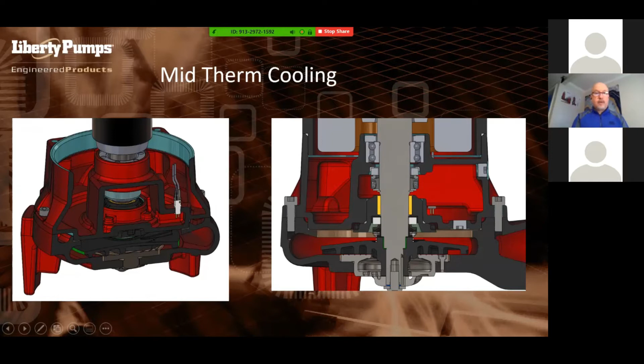And then there's a smaller chamber of oil for the seal area and the seal leak detection probe, so for the lower seal. And I'll show you here a couple other manufacturers' designs, but you can see these are completely enclosed or isolated plates. So you've got an upper chamber of oil and a lower chamber of oil. So anything that's being pumped at a lower temperature might be dissipating the temperature in the oil at this chamber, but it's not really able to cool or lower the temperature in the upper chamber around the stator and rotor assembly. So that's what we're calling the mid-therm cooling type design that we use.